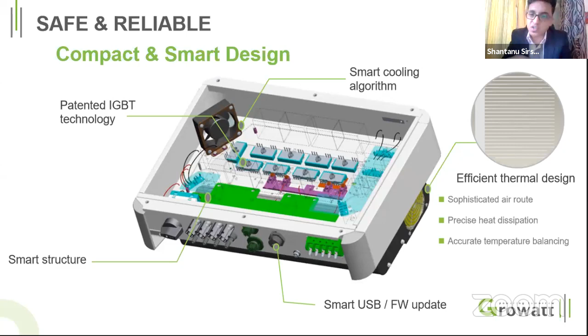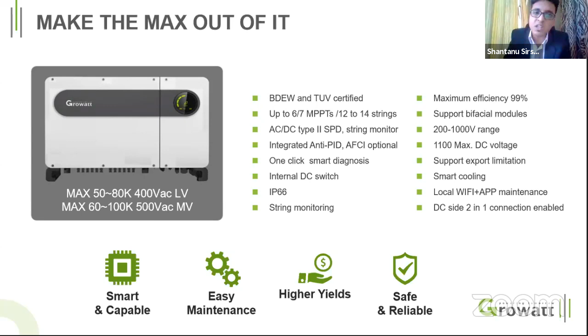Coming to the MAX series for the Indian market, we offer 50 kilowatt up to 80 kilowatt in 400 volts, and 60 kilowatt up to 100 kilowatt in 500 volts. There are two models: one with 6 MPPTs and 12 strings, and one with 7 MPPT and 14 strings. All these inverters come with type 2 protection on both AC and DC side, and IP66 protection. We will go a bit more in brief about this product in the coming slides.